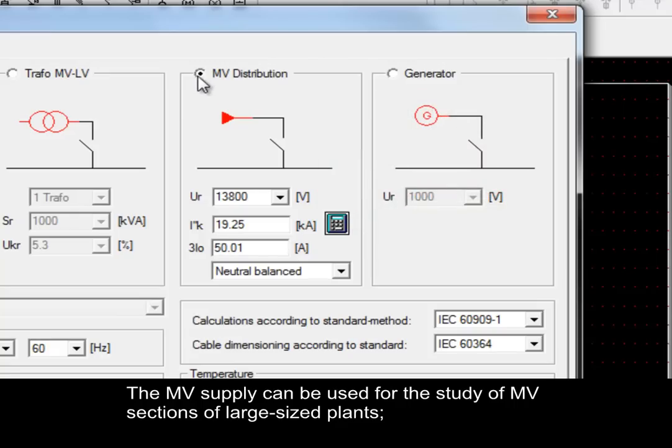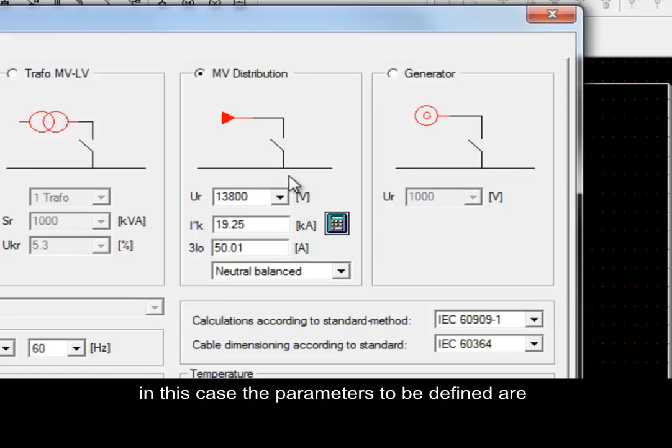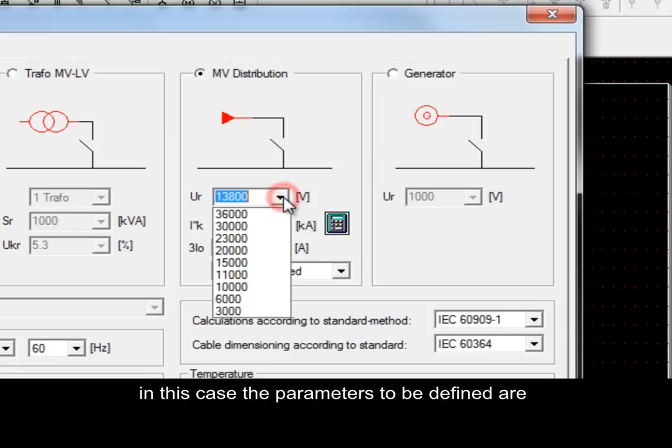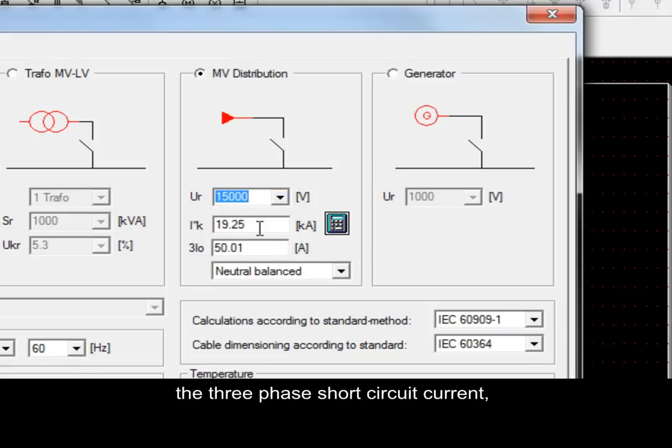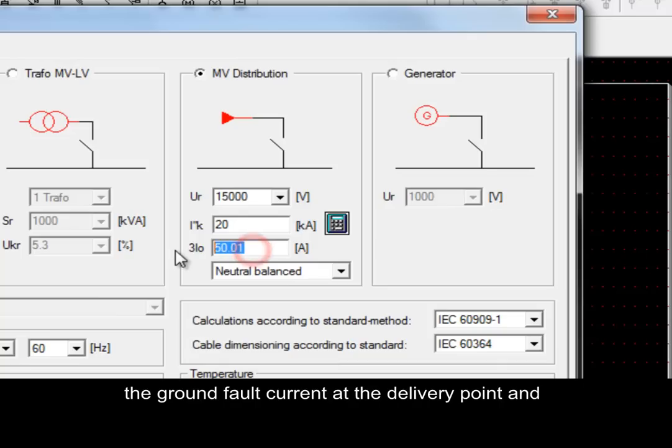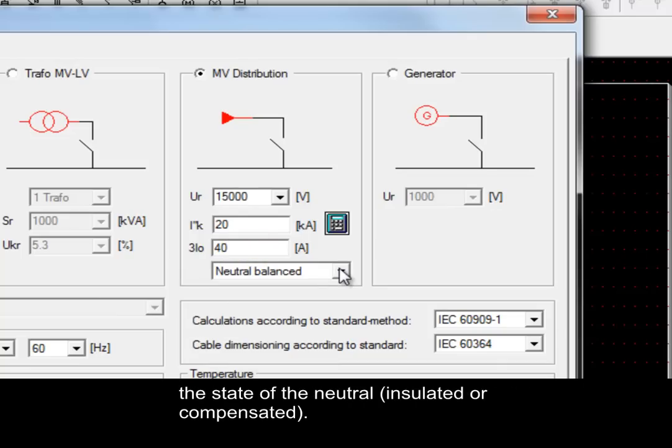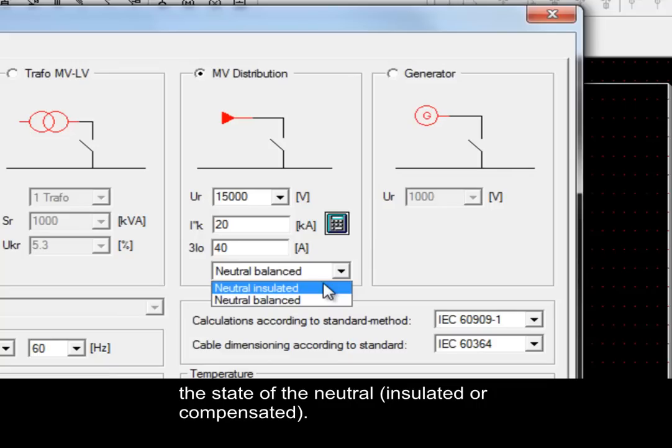The Medium Voltage Supply can be used for the study of Medium Voltage sections of large-sized plants. In this case, the parameters to be defined are the rated voltage, the three-phase short circuit current, the ground fault current at the delivery point, and the state of the neutral, isolated or compensated.